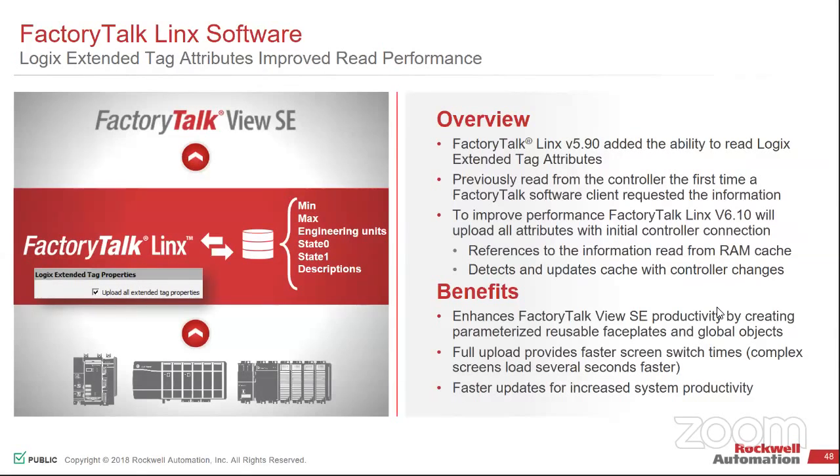Have any of you used the extended tag properties in the controller? How many people knew about this before? Okay, cool. So this is something that came out as of version 34, I think. A lot of the time we have engineering units, things that don't change very often. Instead of using memory for your controller, it's actually saved in non-volatile memory, so it doesn't take space from your 2 meg controller, that's all hidden in the background. And now you can interface with the HMI.